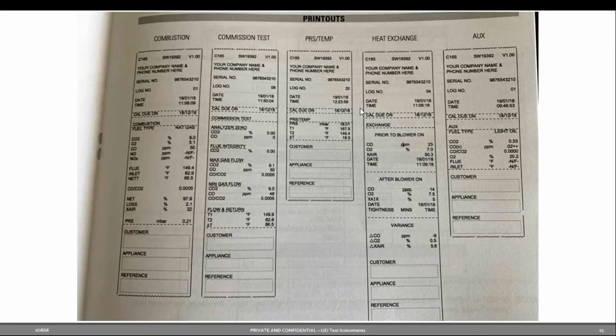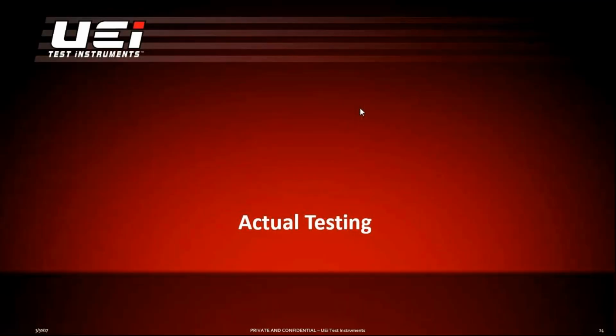Our combustion analyzers, when you have the printer option, provide you with a lot of different tests you can do. If you take a quick look, there's a combustion test, a boiler commissioning test, and if you just are checking and want documentation of your pressure and temperature, there's a report for that. There's also a heat exchanger test that one of our combustion analyzers does, and an auxiliary one that just shows you all your current values.